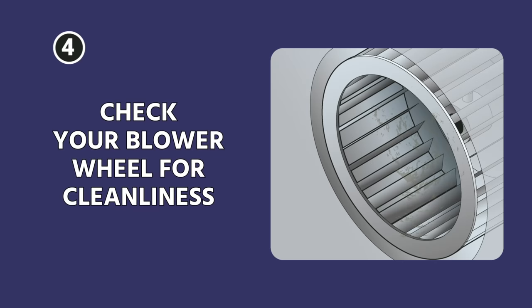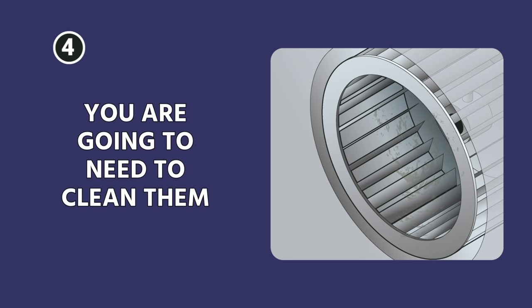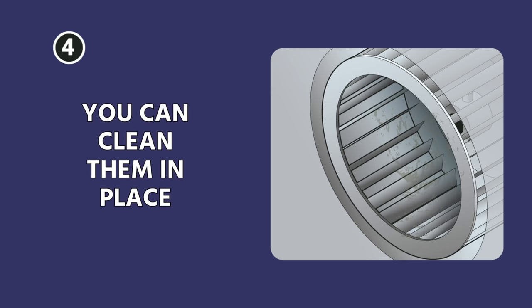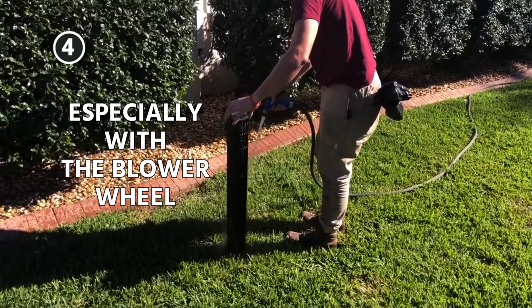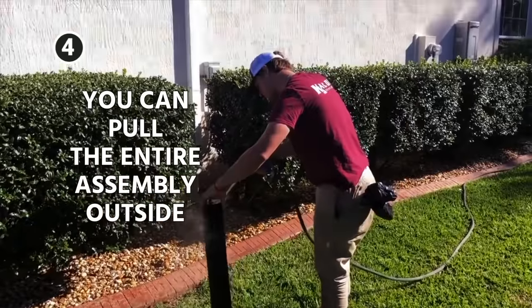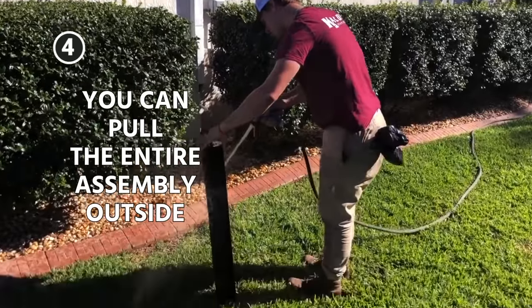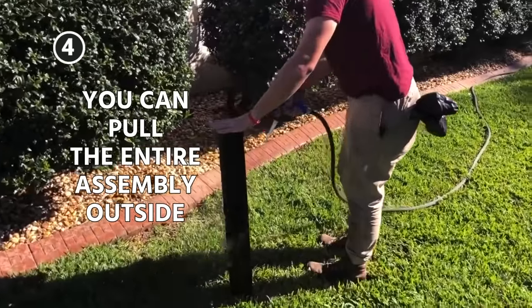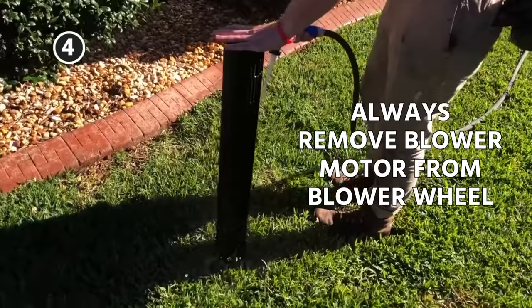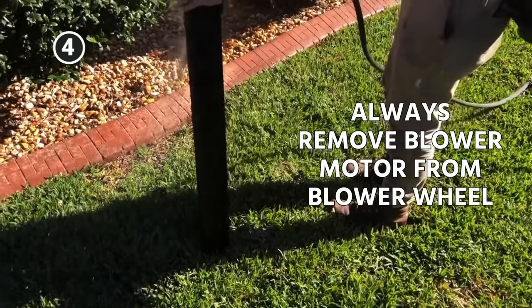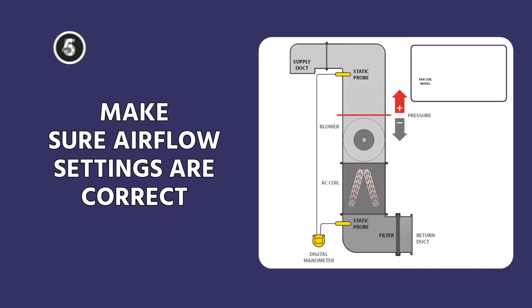Next step: check your blower wheel for cleanliness. In both of these cases, if they are dirty, you're going to need to clean them. If you can clean them in place, great, but in many cases you're going to have to pull them outside. Especially with the blower wheel, you can pull the entire assembly outside and wash it out in the yard. Always remove the blower motor from the blower wheel before you attempt to clean it.